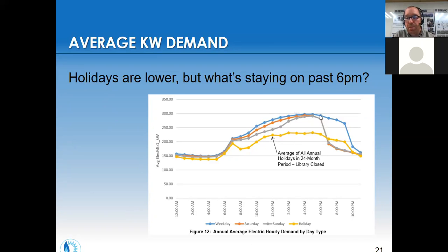Looking at the time of day that things turn off in the evening, a weekday normally turns off around 9 p.m. A weekend seems like it turns off about 6 p.m. But an interesting case in this example, Sundays, the library closed at 2 p.m. So an interesting question would be, why was the schedule not changed to reflect that 2 p.m.? So that would be a significant savings on Sundays.